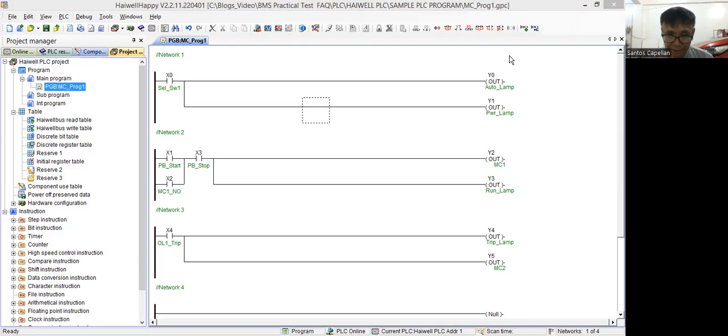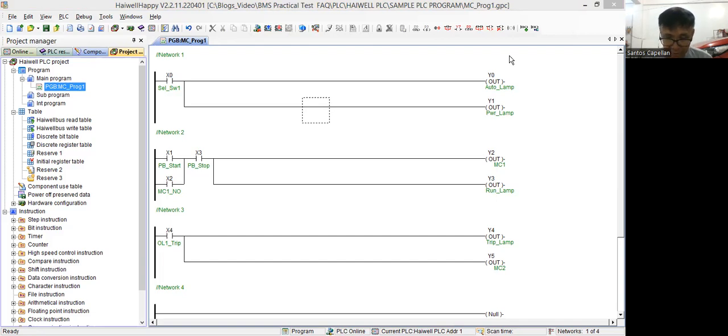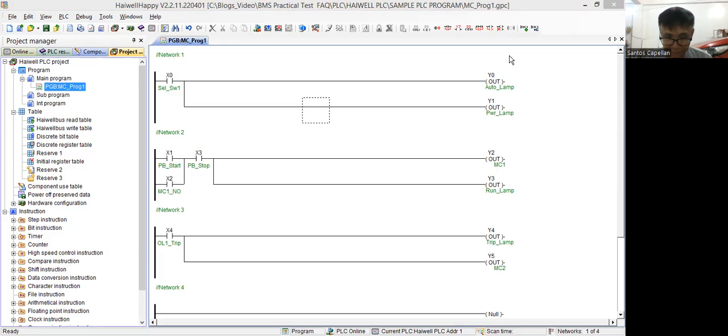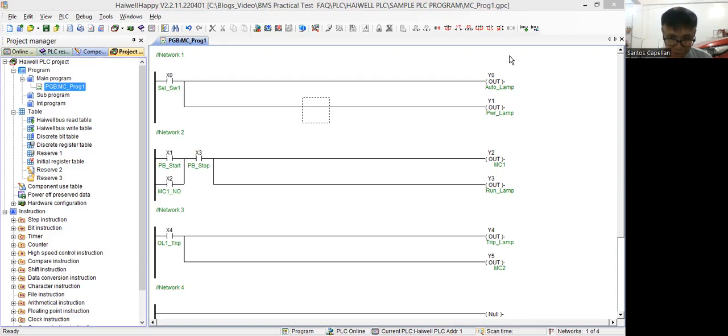Now, as you can see, the PLC tried to energize the contactor here. Then it will PLC also is the one driving this indication lamp, the run lamp. Now this is the real time status of the IO is being reflected in the PLC also. I like this. Then the wiring is very easy because you need to just press this, then insert the cables or the wire. Now we can show you how, if you will try to trip this, then based on our program, the PLC should start the standby motor here. Or the standby fan.